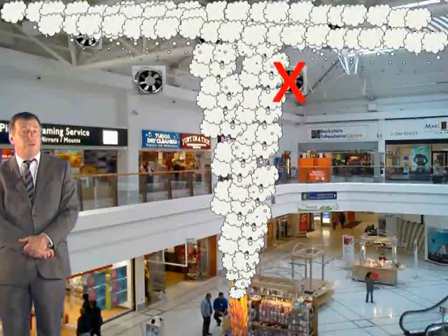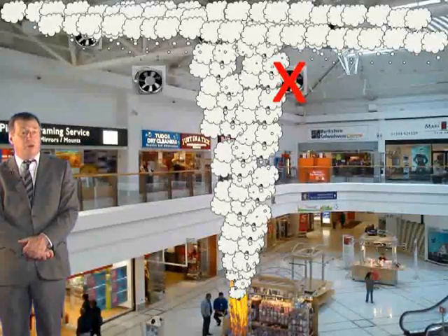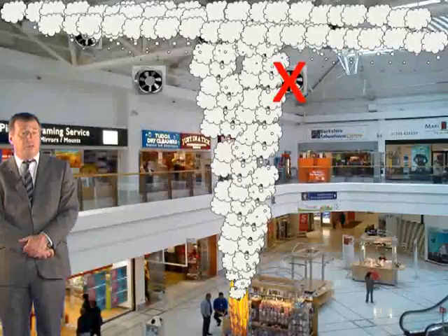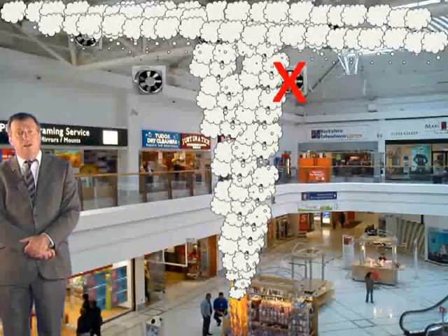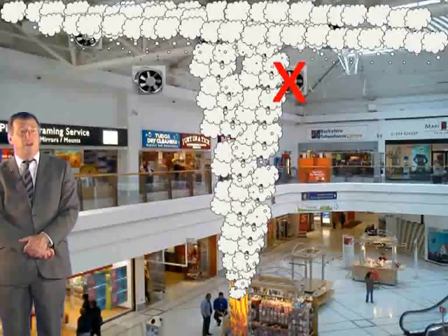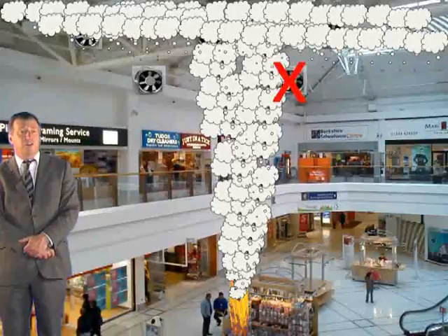For example, the fire might be located directly beneath one of the fans, thereby exposing it to temperatures greater than it was designed to withstand. In other words, even with one of the fans not operating, the other remaining fans should have an aggregate capacity of at least the required volumetric extraction rate.